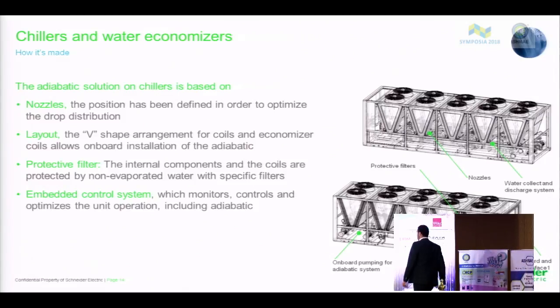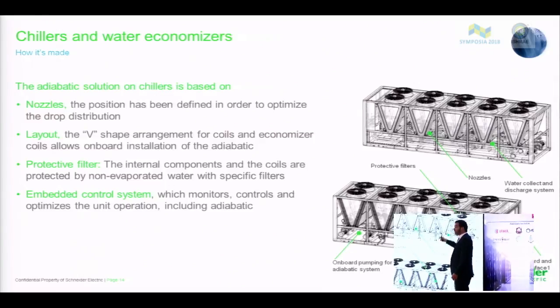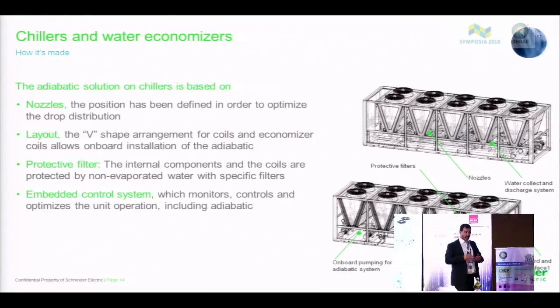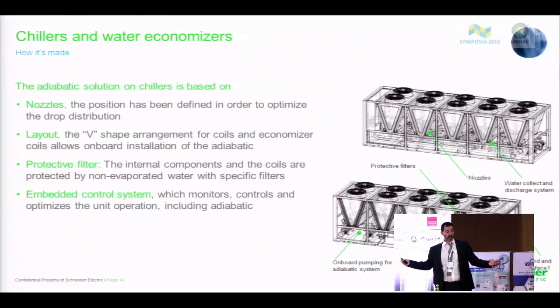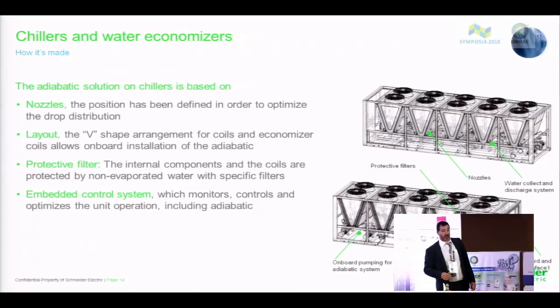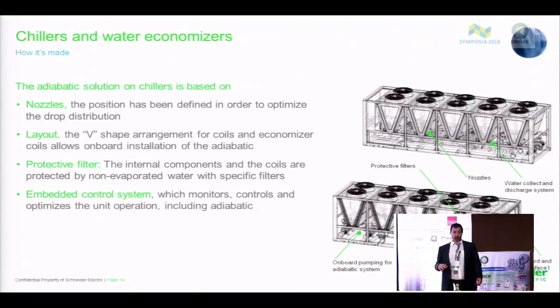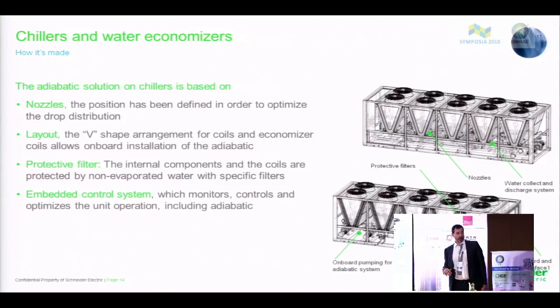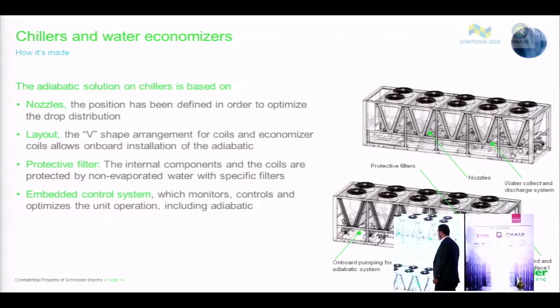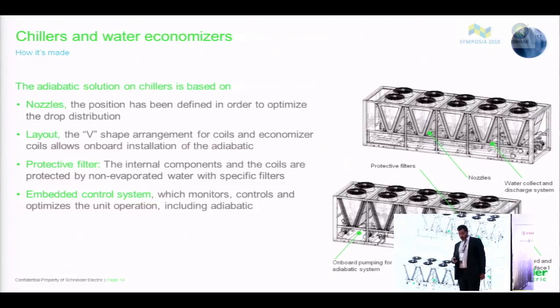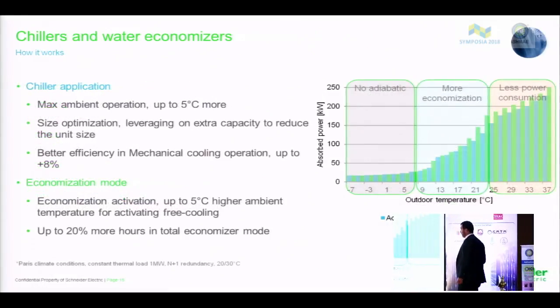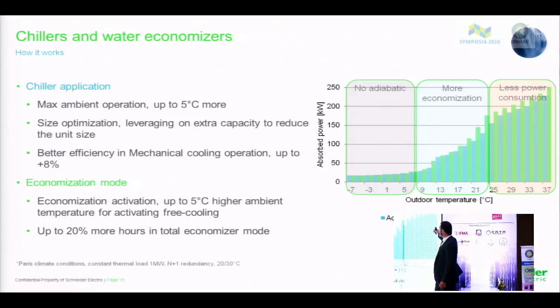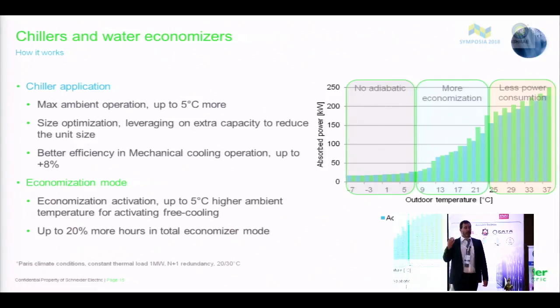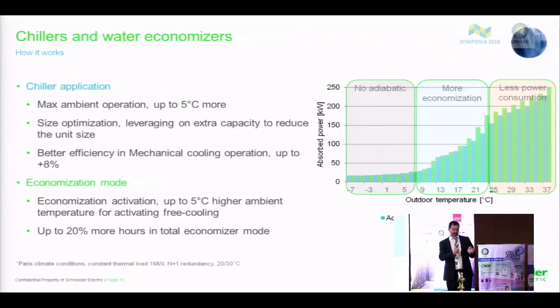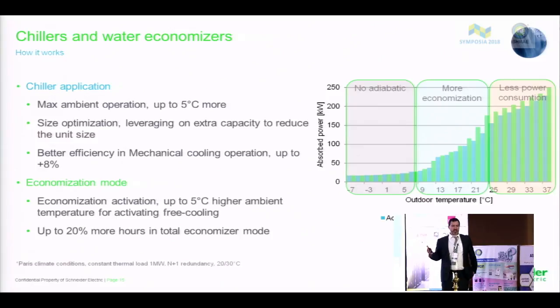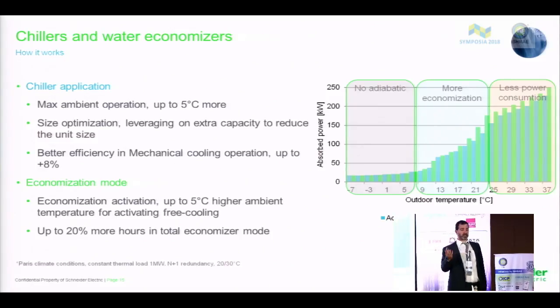So this means that if the ambient temperature is, let's say, 45, and the wet bulb is 30, whatever it is, this means that the inlet temperature is around 38, something like that. It means that there is a huge saving of energy for that. And there is therefore more efficiency at high ambient, but more and more, if we design a 20/30, this means that we can start the free cooling at 27.